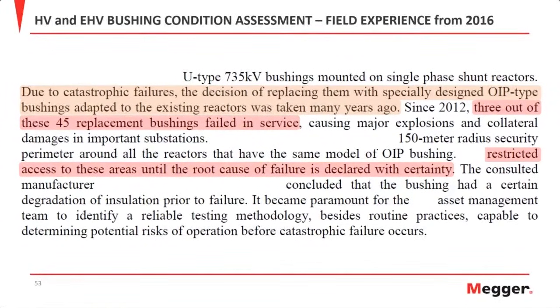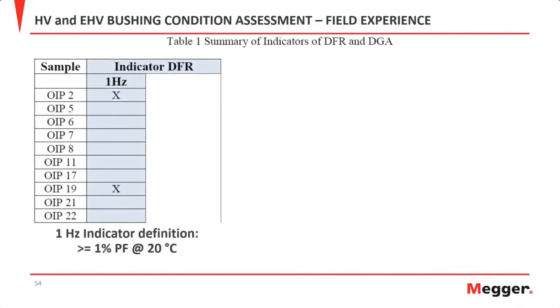The bushing manufacturer was then contacted to do some additional tests, and this is what they found. The first thing that they did was a DFR sweep on the bushings, but I want to focus solely on the 1 Hertz. And when we look at the 1 Hertz, we saw that 2 of these bushings had high 1 hertz. So this would be 1 hertz above 1% power factor at 20 degrees C.